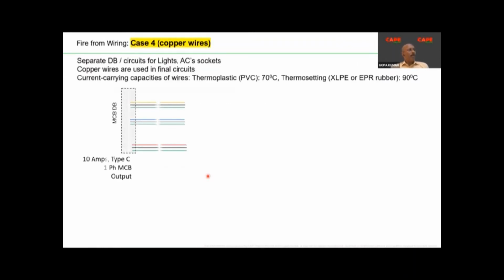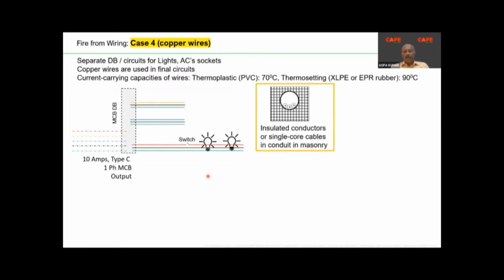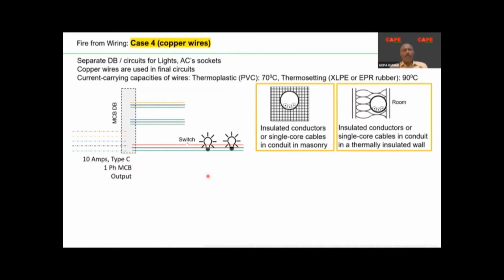Number 4, copper wires. As you are aware, in all the final circuits, that means from the last MCB DB up to the final equipment, we always use copper wire. For selecting these copper wires, we have to go through certain critical types of installations. We have to evaluate the type of installation, such as how we are routing the line, whether it is through a conduit or open wiring. Because in a conduit, the most important thing is that wires will create heat. Wires have certain resistance, and if the resistance is higher, heat is higher. If the heat is higher, the installation is going to be in trouble.